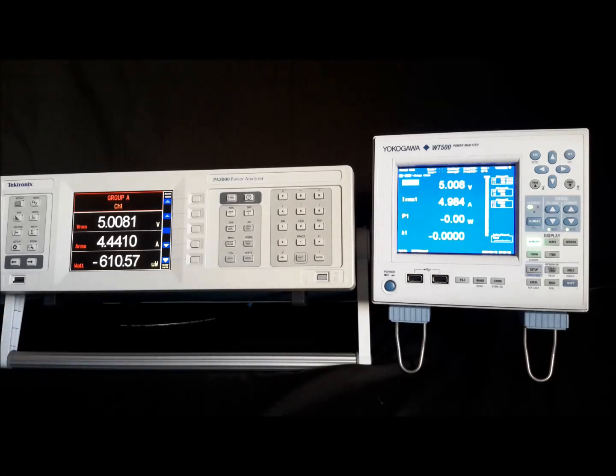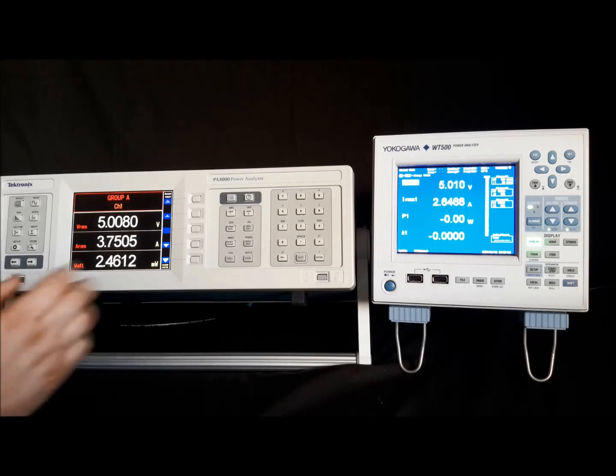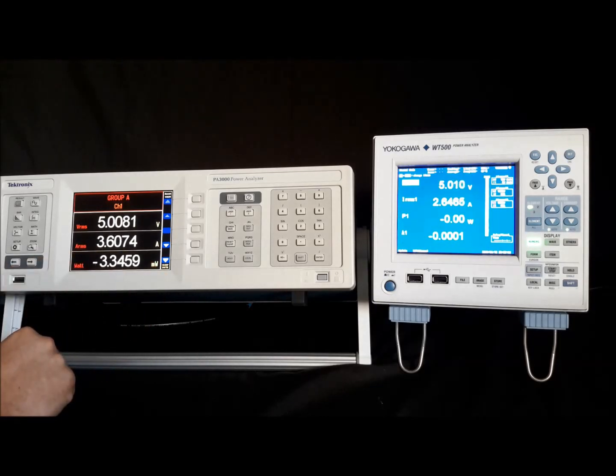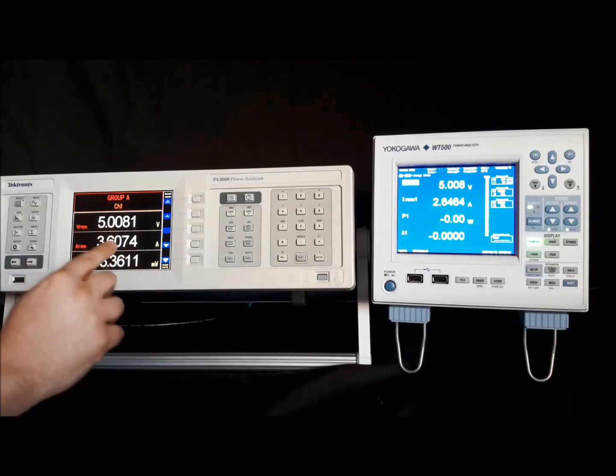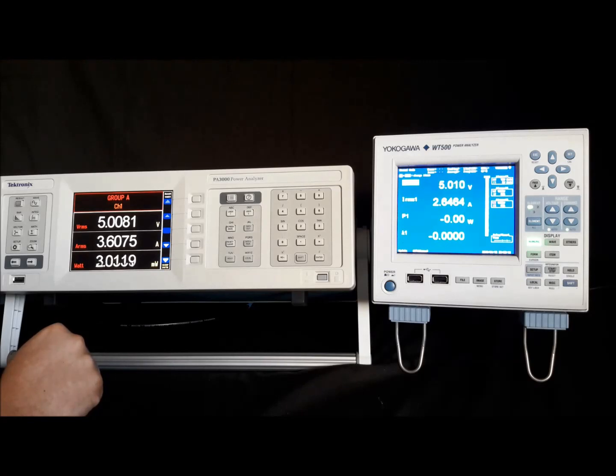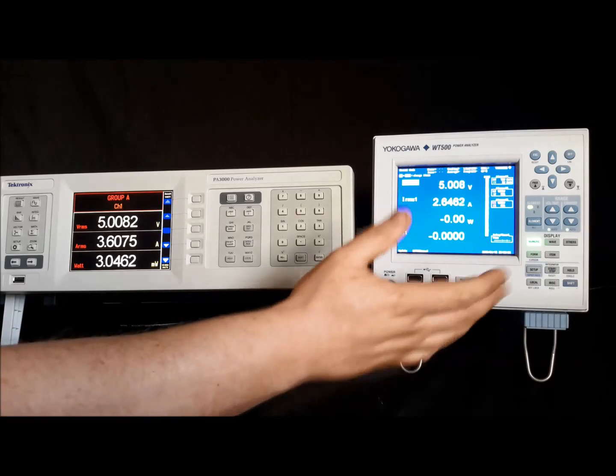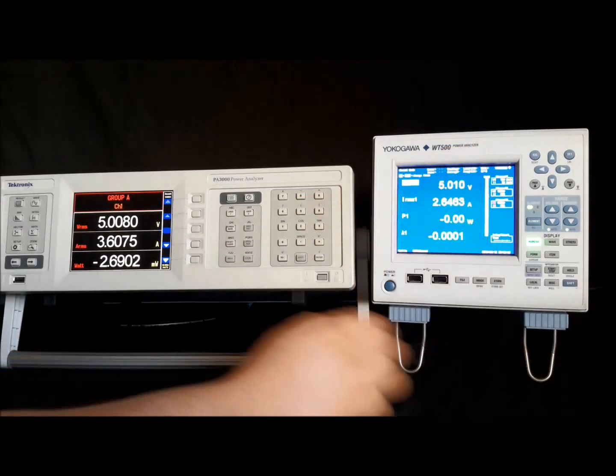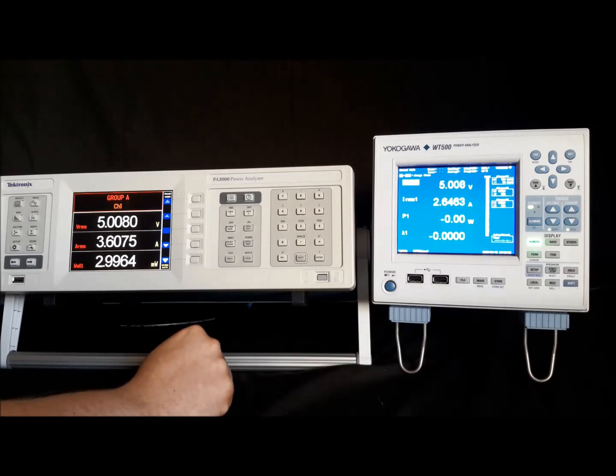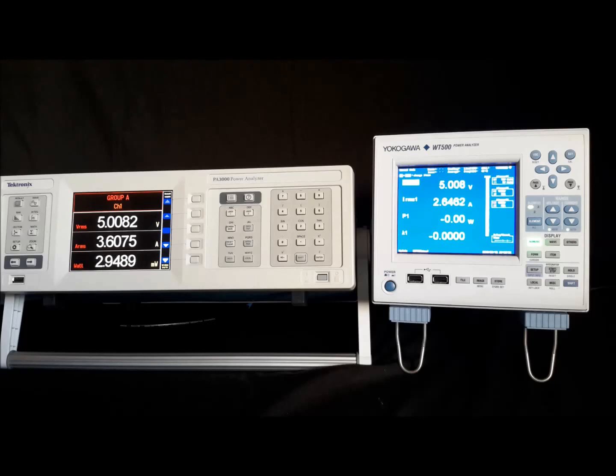I'm expecting the Yokogawa to drop down on the current when I go to 1 megahertz, but then the Tektronix drops down as well, maybe not as far as the Yokogawa, but considering that the 5 amp input across the 1 megahertz bandwidth on a 1 megahertz unit is showing 3.6, we know that high frequency current measurements and voltage measurements do have a greater deviation, but that is quite high. Again, I'm going to disregard the fact that this is showing at half the measured unit, because at 1 megahertz for a 100 kilohertz unit it's not built to perform at the 1 megahertz. Okay, let's reset that back to 50. Now let's have a look at the voltage. Same again, 1 megahertz.